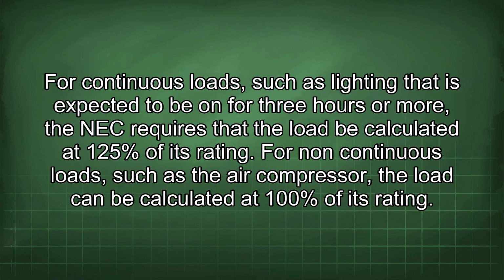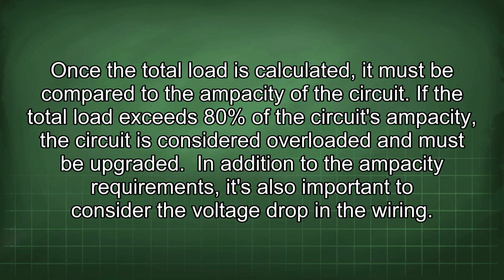To perform a load calculation, each load's amperage requirements need to be determined. For continuous loads, such as lighting that is expected to be on for 3 hours or more, the NEC requires that the load be calculated at 125% of its rating. For non-continuous loads, such as the air compressor, the load can be calculated at 100% of its rating. Once the total load is calculated, it must be compared to the ampacity of the circuit. If the total load exceeds 80% of the circuit's ampacity, the circuit is considered overloaded and must be upgraded.